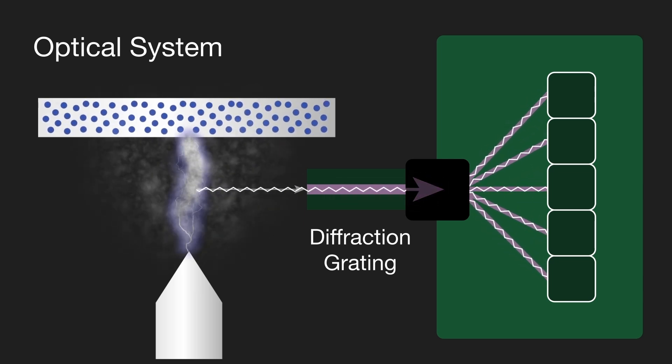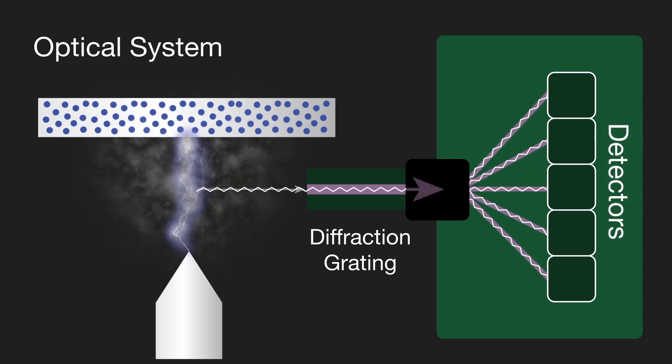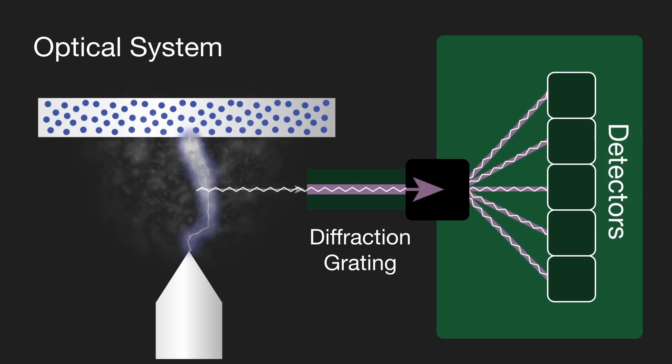A diffraction grating in the spectrometer separates the incoming light into an element-specific wavelength and a corresponding detector measures the intensity of light for each wavelength. The intensity measured is proportional to the concentration of the element in the sample.